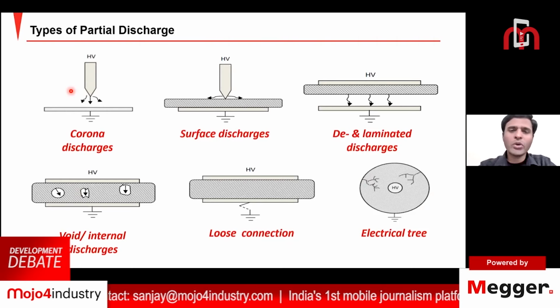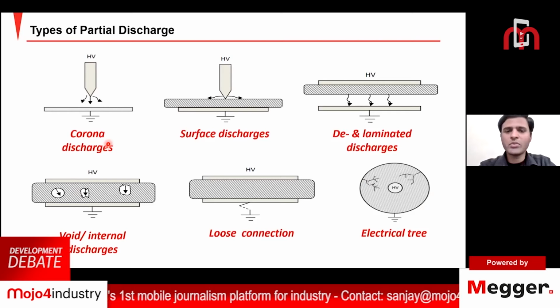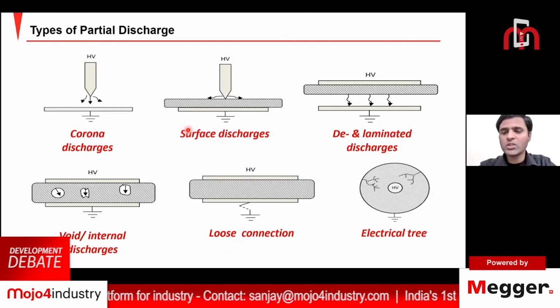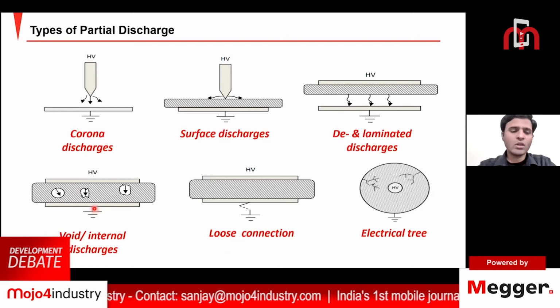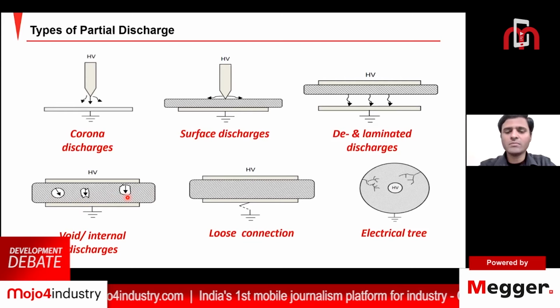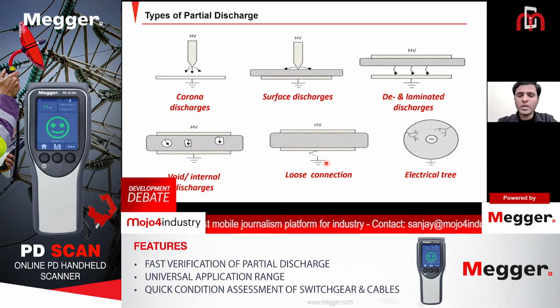We can see corona discharges in switch yards and on transmission lines in the air. As you can hear, there are some sounds because of corona discharges, and they can be visible with the human eye. At the surfaces of different materials, surface discharges can lead to partial discharge. Then there are delaminated discharges. Because of low quality material, there can be voids or internal discharges in the dielectric material. Due to a loose connection, there can be sparks, which can lead to discharges at terminations. Also, electrical treeing is a phenomenon seen in porcelain material and in cables, which can increase the aging of a particular asset if it is unattended.